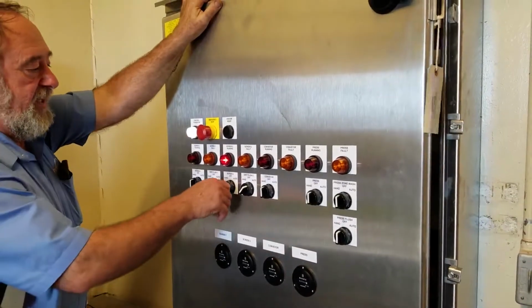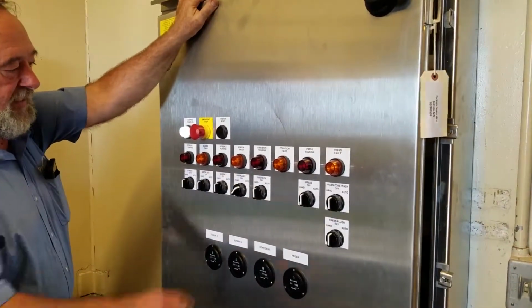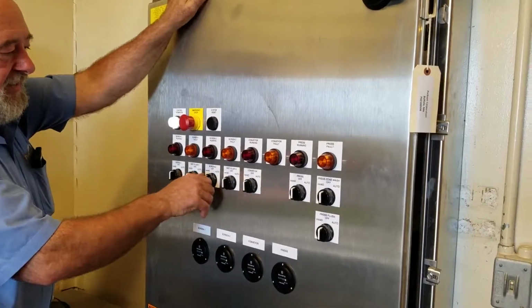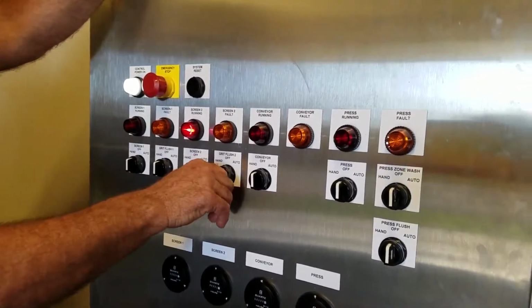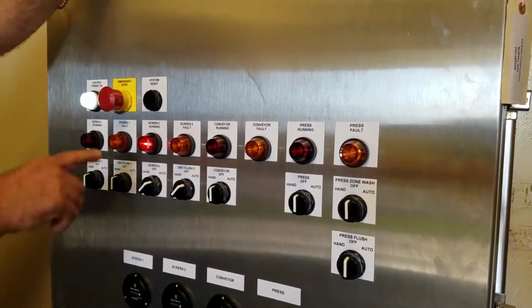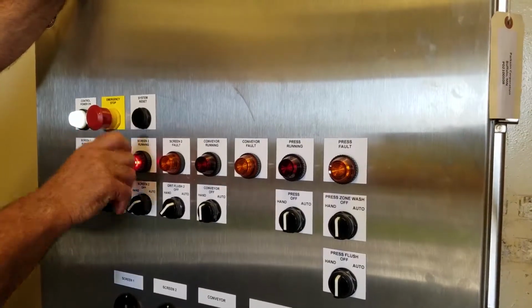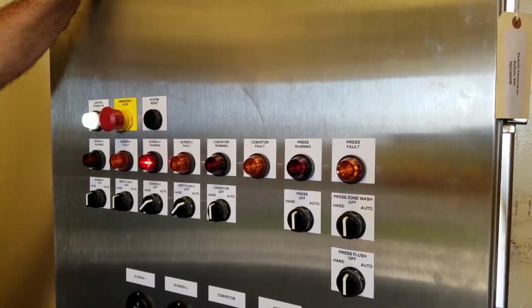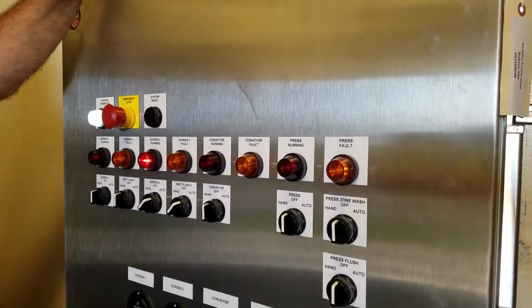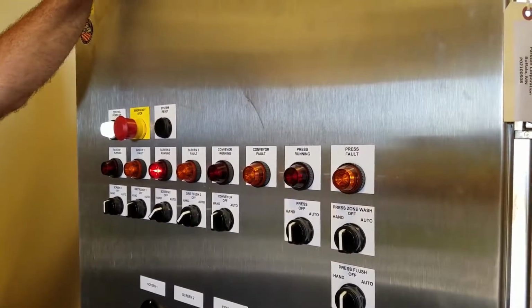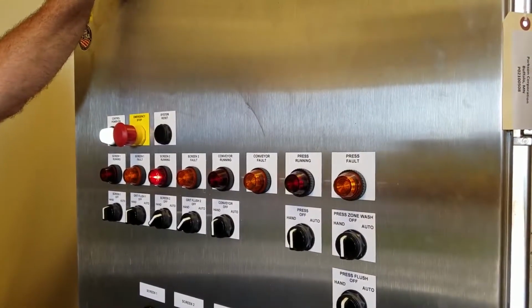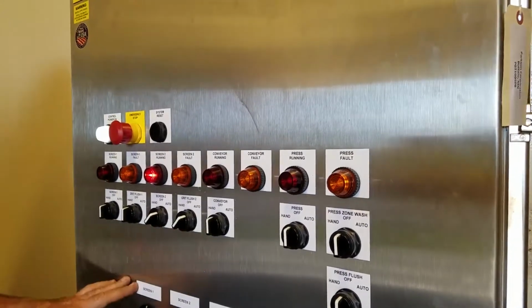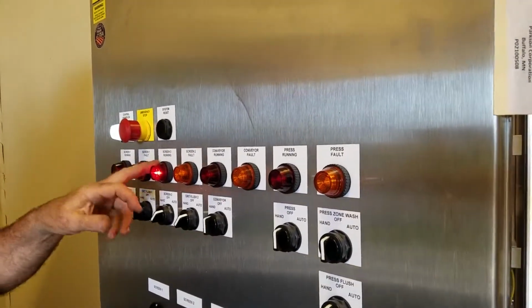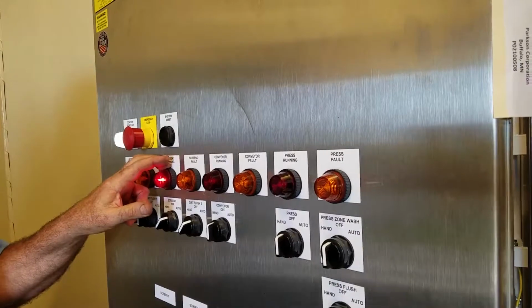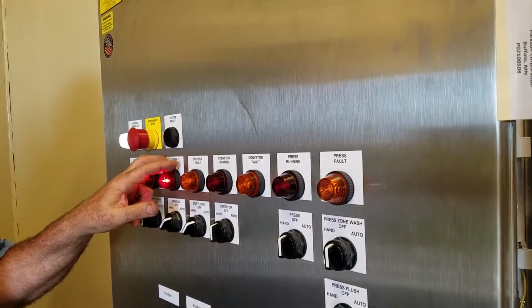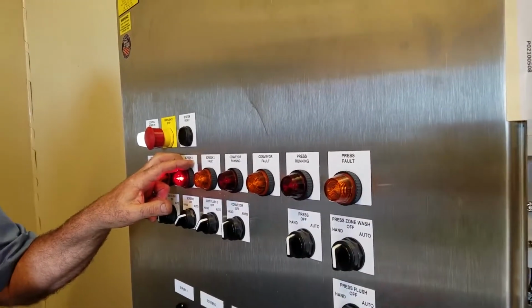Now I'll show you something else. When you get everything all hooked up, if you hold this reset button down for 5 seconds, it's going to start everything in auto cycle. It'll start the press, the conveyor, screens, all that stuff. Anything in auto will do that. But right now, because it thinks it's seeing a high level because something's wrong with one of the parameters inside that little box, it's telling it you got a high level and it's running all the time.